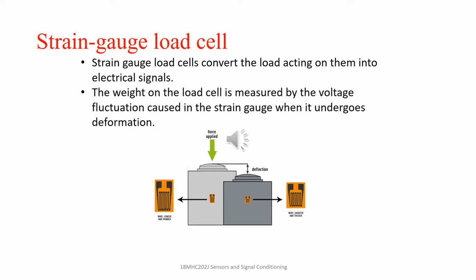Next is the strain gauge load cell. In this type, a strain gauge assembly is positioned inside the load cell which converts a load acting on it into electrical signals. The weight on the load cell is measured by the voltage fluctuation when it undergoes deformation. The gauges themselves are bonded onto a beam when the weight is applied. Modern load cells have 4 strain gauges to increase the accuracy, 2 strain gauges in tension and 2 in compression.